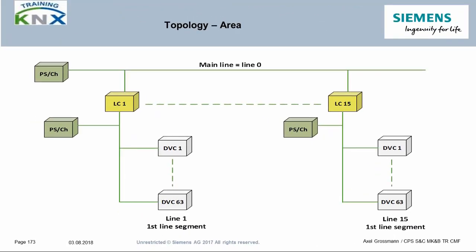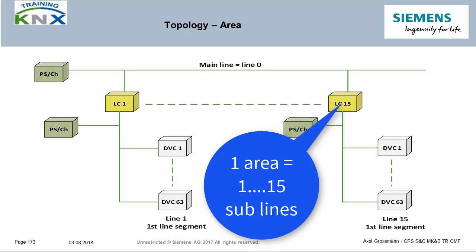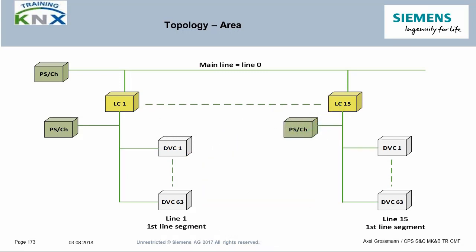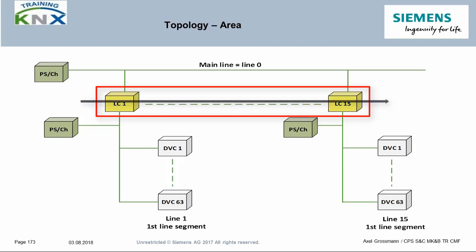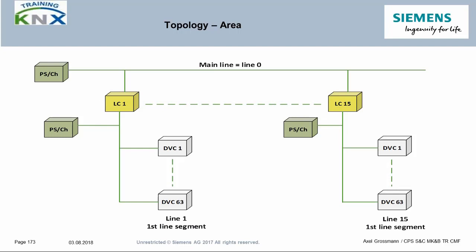Each area in the KNX system can contain a maximum of 15 sublines. These sublines are networked with each other via the main line. The line coupler serves as the coupling element. It connects the first line segment with the main line communicatively, but also represents a galvanic separation between the two lines. If it is not sufficient to equip the sublines with the first segment — for example because more than 64 subscribers are required — further three more segments can be set up and connected in parallel.